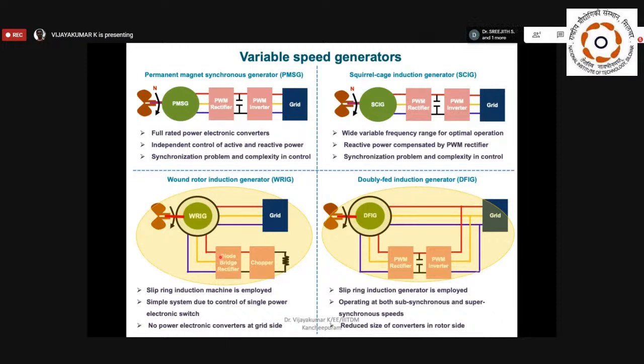will work as a generator above synchronous speed. Above synchronous speed, for a 4-pole 50 Hz system, 1500 RPM is the synchronous speed. It will operate as a generator from 1500 to 1520 RPM. But in this case, we can operate the machine as a generator below synchronous speed also, say 20 RPM below, so 1480 also I can operate as a generator.